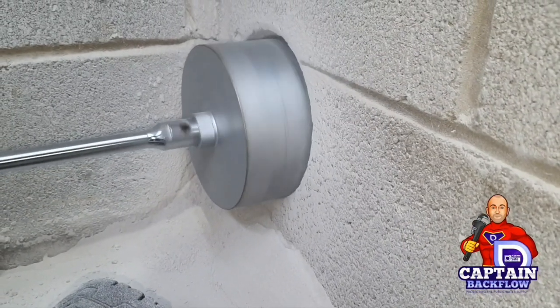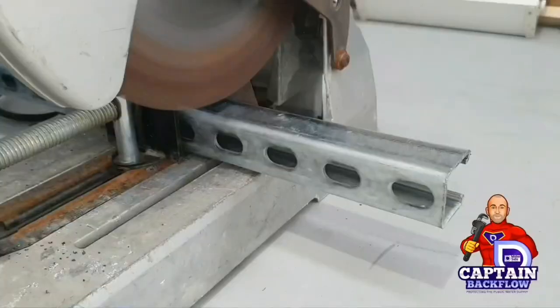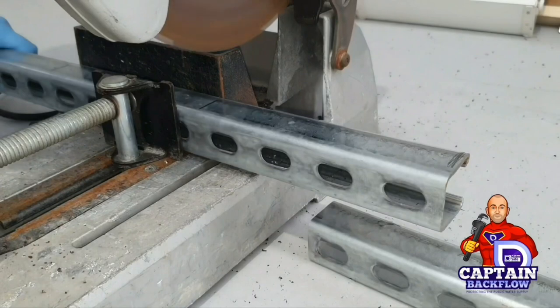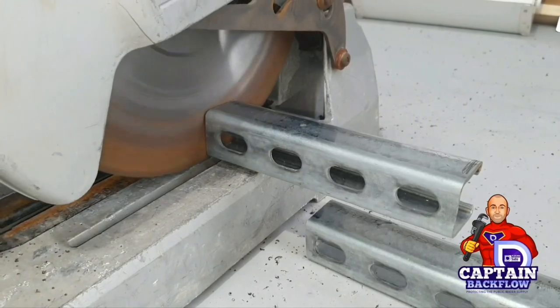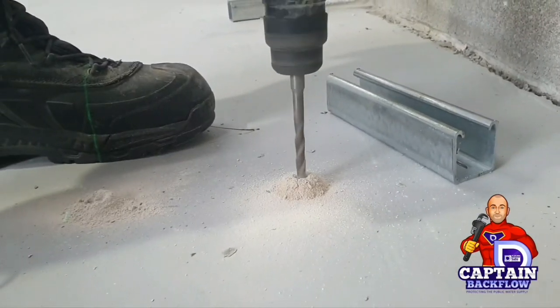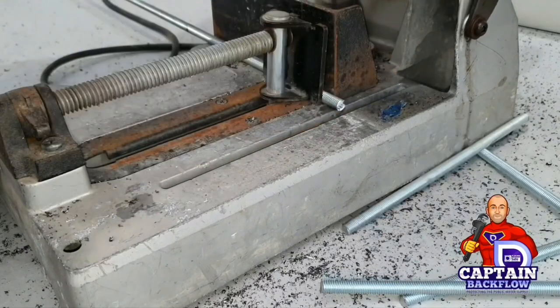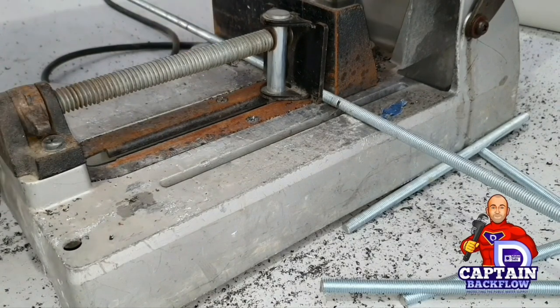Alan, this is going to be super fast on some bits and a bit slow on others as I voice over this. We're using a six-inch diamond core bit — we use six inch so we can get through the wall with the tee or elbow if need be. If you use a five inch you struggle. We're then using our Makita chop saw with a TCT blade rather than an abrasive disc — it's a fast, clean, cold cut. Matt is using laser marking out and we're going to set all the unistrut off the wall. We can also use this chop saw for cutting rod, giving a clean cut ready for nuts to screw straight on. We're just prepping our bracketry at the moment.